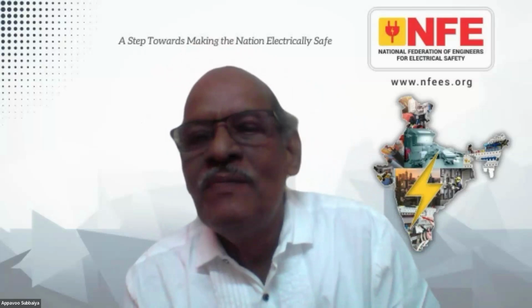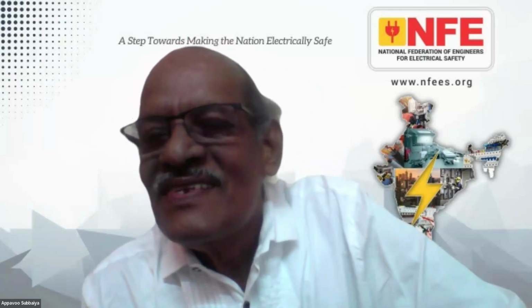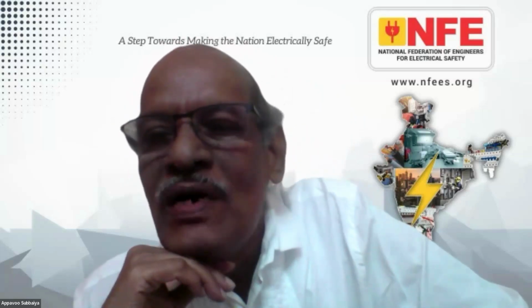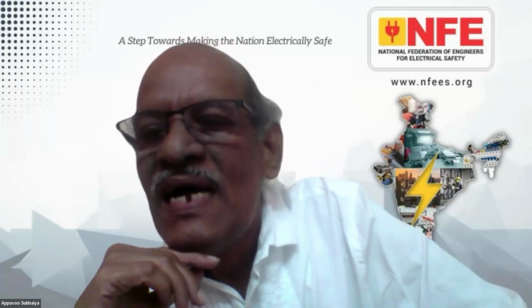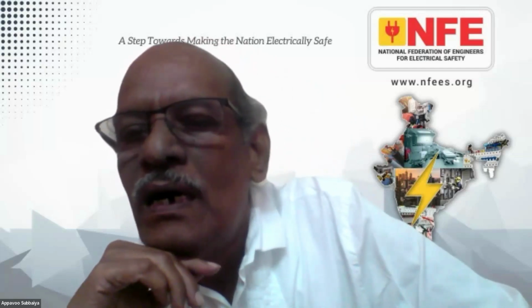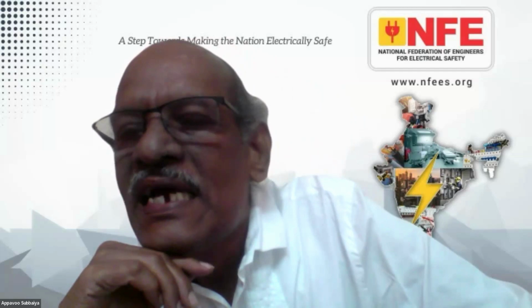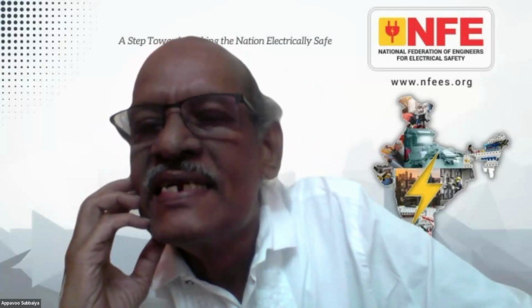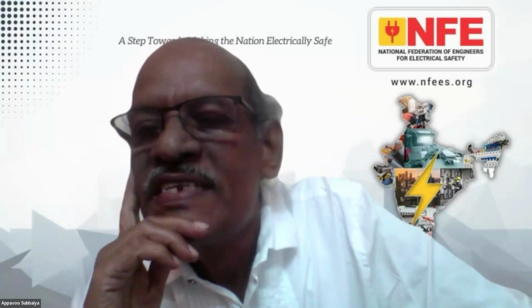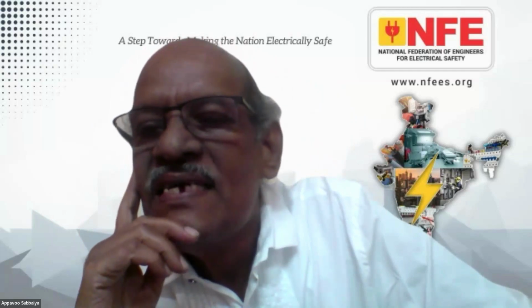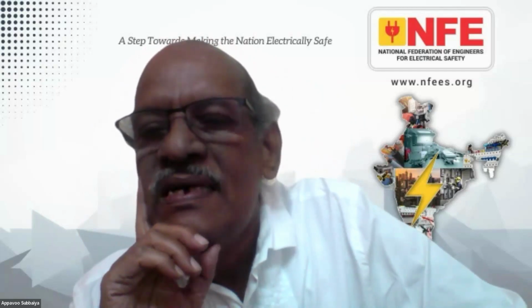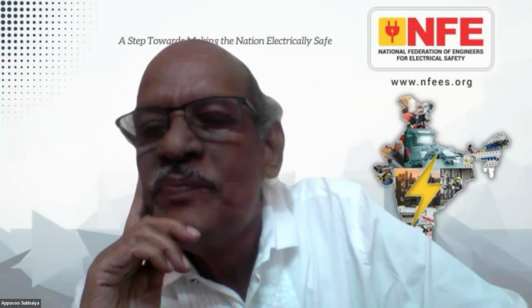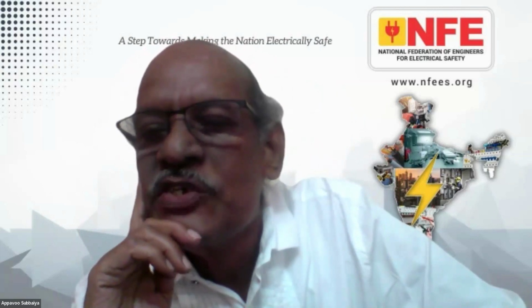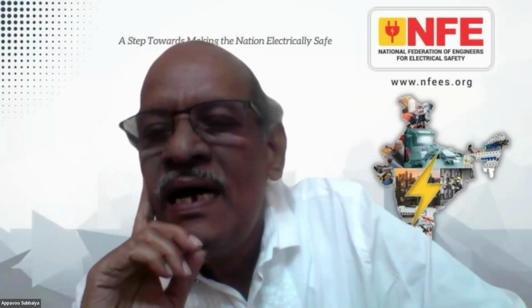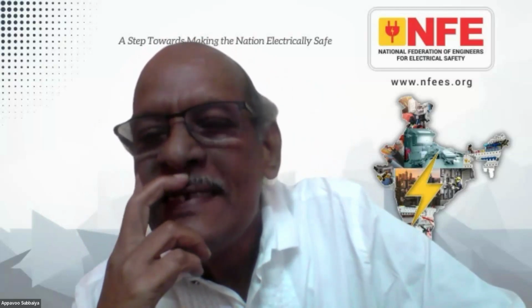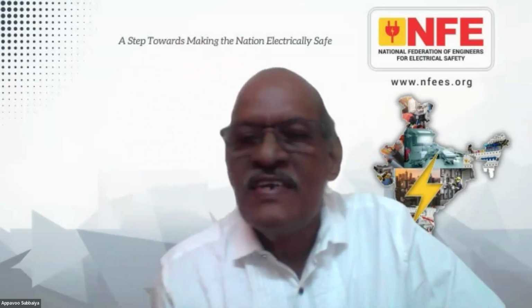There is another question from Manivannan Ayyappan: in an installation without RCD (I think this is RCD, not RCB), the consumer's earthed terminal is connected to the earthed neutral of DISCOM. There was a leakage and a shock felt in consumer premises. This problem was rectified by disconnecting the interconnection between the consumer's earthed terminal and the earthed neutral of DISCOM. Please suggest the correct solution. It's a fantastic question.